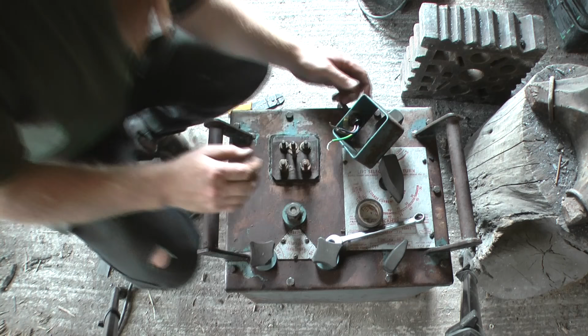Partway through wiring it to the mains, and I thought I'd show this bit just in case anyone out there has one of these and wonders how it's wired up. This terminal cover comes off, and underneath it says 415, 440, E referring to the middle one, 240, and 0. So for me, I'm going to use 0 as neutral, 240 as the live, and the middle one is always earth.